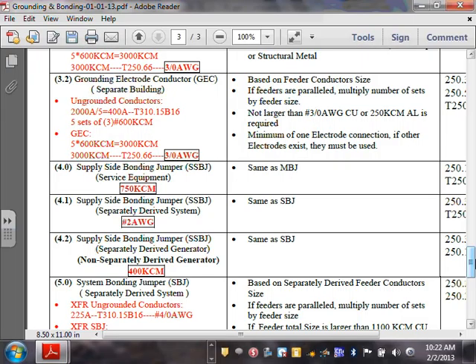What was it for 600? Anybody? 250.66? Table 250.66, copper, 1 aught? 1 aught for copper, right? Over 350 through 600? Okay, 1 aught copper. So instead of using a 750, daisy chain them, big wire to work with, land, torque, then you can use 1 aught from one conduit at a time. That's where it becomes an alternative.